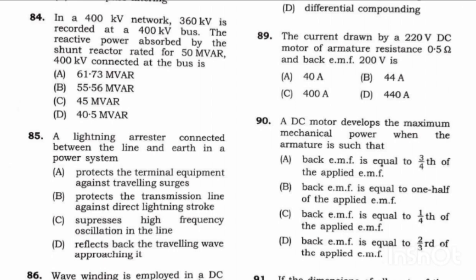84 number question to hold. In a 400 kilovolt network, 360 kilovolt is recorded at a 400 kilovolt bus. The reactive power absorbed by the shunt reactor rated for 50 MVAR 400 kilovolt connected at the bus is A. 61.73 MVAR, B. 55.56 MVAR, C. 45 MVAR, or D. 40.5 MVAR. And the correct answer is D.